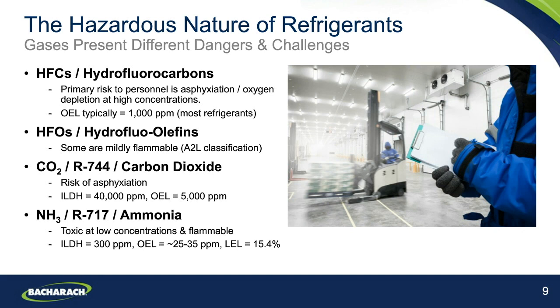Obviously, it has a much lower global warming potential than many of the HFCs. But of course, CO2 can present some risks as well. There is a risk of asphyxiation. CO2 presents an immediate danger to life and health at 40,000 parts per million, and the typical exposure limit for CO2 is generally around 5,000 parts per million, which is where we would typically tend to see systems going into alarm from.